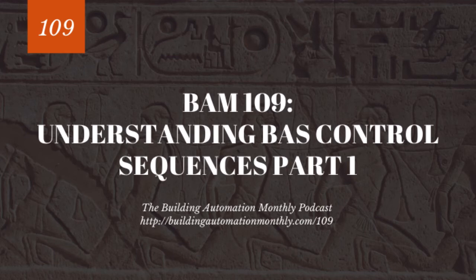Here's what you're accomplishing: first, you make sure you don't miss anything, because it becomes readily apparent when these things are broken out into categories whether you're missing a control mode, an enable mode, or a safety mode. It's a lot harder to spot that when it's buried in that mess of words in the sequence. When it's broken into neat categories, it becomes obvious.